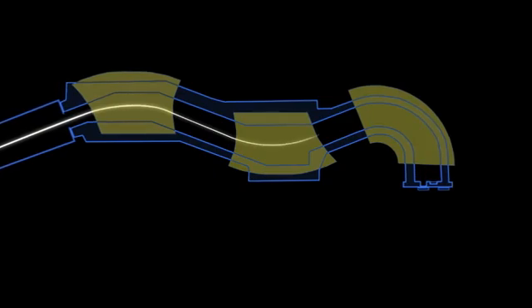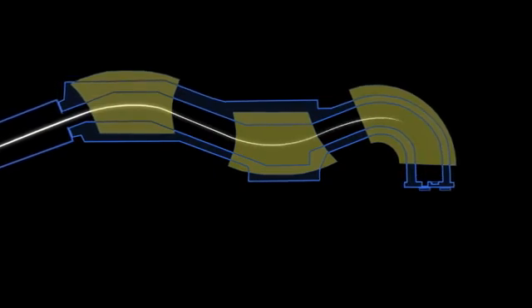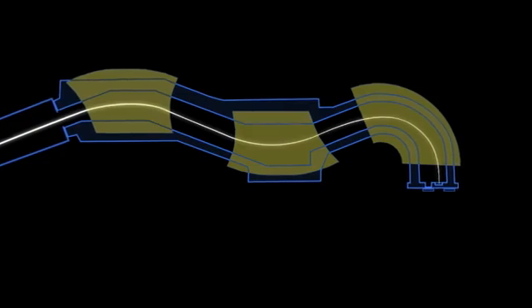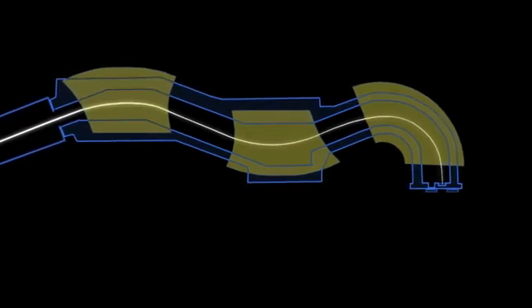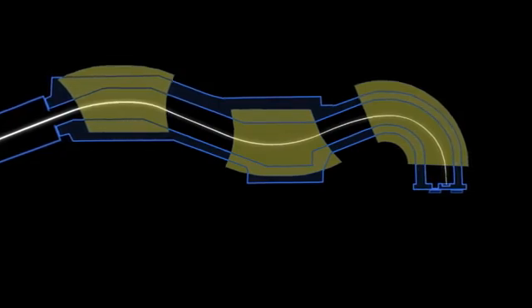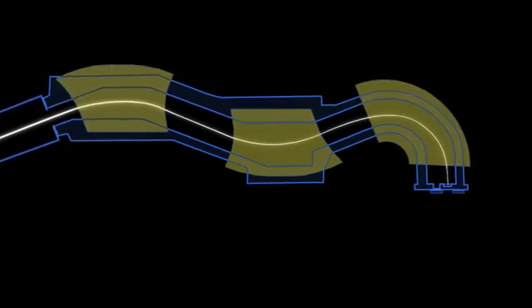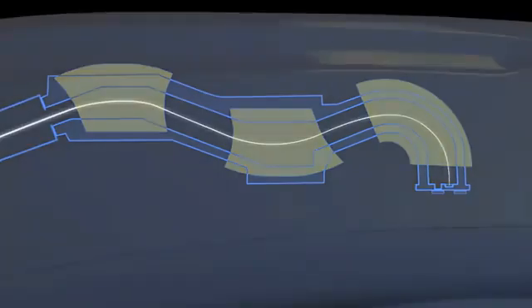The electrons travel along a slalom path within the flight tube. Three pairs of magnets on either side of the flight tube cause the electron beam to bend through the turns of the slalom. This process not only positions the beam to strike the target, but it also further focuses the beam to a diameter of one millimeter. The design of the magnets enables them to focus electrons of slightly different energies onto the same point on the target. This is called achromatic behavior.